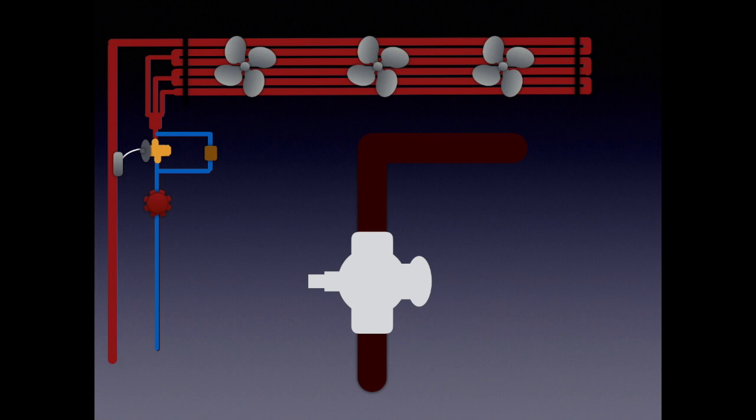And all the way back to the case. And the way this is all happening is this differential valve that I talked about at the beginning of these slides. The differential valve never shuts completely. What it does is when one system goes in defrost, the solenoid will close it. But still allow pressure. So that the receiver pressure remains higher than the liquid header pressure. You'll usually find probably a 40 to 60 pound difference.